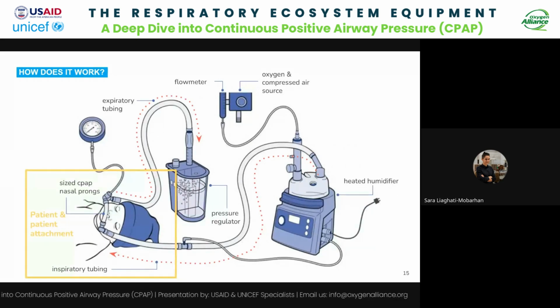So in the expiratory flow, this is the movement of gas from the patient's airways back to the CPAP device. So think about this as inhale and exhale. So in the exhalation, the patient exhales. So the expelled gas, any carbon dioxide, any residual oxygen, is directed back, and the flow pushes it away from the patient so that they're no longer inhaling carbon dioxide and things like that. And then it's also, during this process, still providing a constant flow of gas to maintain the lungs. So the airways don't collapse, as Leah showed, the balloon stays open. All of this loops into the next component, which is the pressure regulator.